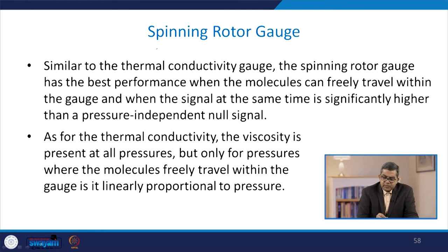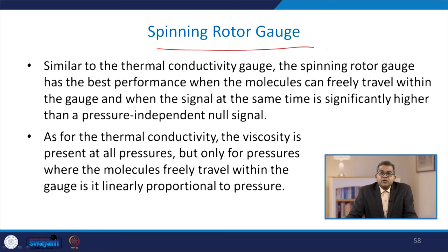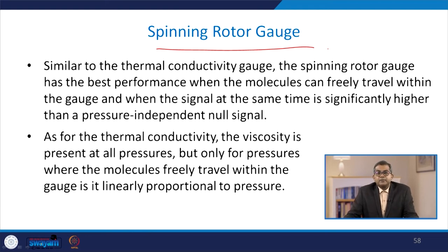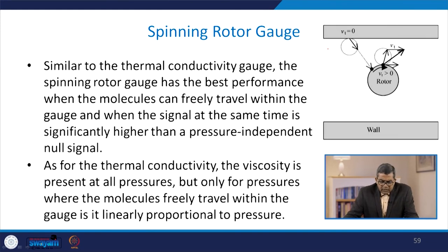The spinning rotor gauge, similar to thermal conductivity gauges, has the best performance when molecules can freely travel within the gauge and when the signal is significantly higher than the pressure-independent null signal. As with thermal conductivity, viscosity is present at all pressures, but is linearly proportional to pressure only in the regime where molecules freely travel within the gauge.